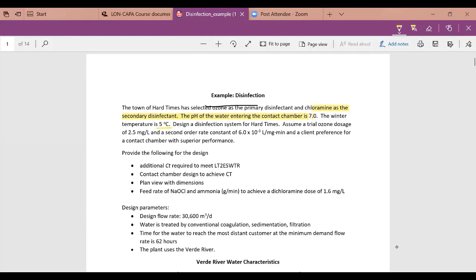The pH of the water entering is 7.0. We have a winter temperature of 5°C. We'll assume a trial ozone dose of 2.5 mg/L. A second-order rate constant was provided from laboratory testing, and the client wants a contact chamber with superior performance — meaning close to plug flow. We need to determine the CT requirements according to the Long-Term Enhanced Surface Water Treatment Rule and design the contact chamber.